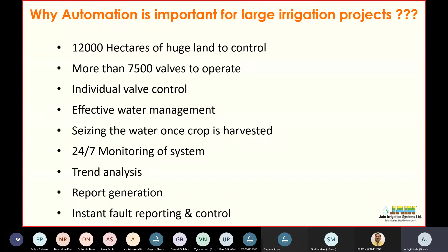Then there is a requirement of trend analysis and report generation, to see how the pressure fluctuations were in this system, because it's a large area. There are almost 150 pressure sensors and 150 flow sensors. You need to monitor each and every one, because if one area is closed down, the pressure will increase on the other side. So that is to be monitored. Trend analysis is to be done. Faults are to be instantly reported and controlled. These are the challenges where we required an automated irrigation system, an IoT-based automated irrigation system.